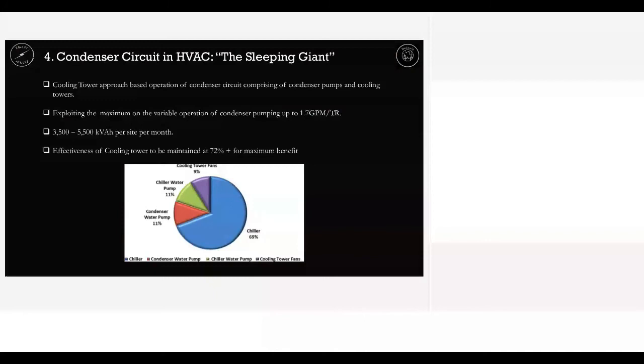So this is a very important pie chart that we call the holy pie in centralized air conditioning. The chiller consumption is showing 69% of the total plant room. Condenser pump and chilled water pump are 11% respectively of the total consumption of the plant room, and cooling tower is 9%. All these things collectively come to 100% of the plant room.